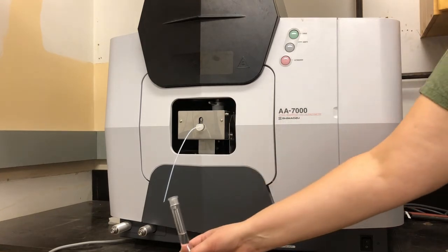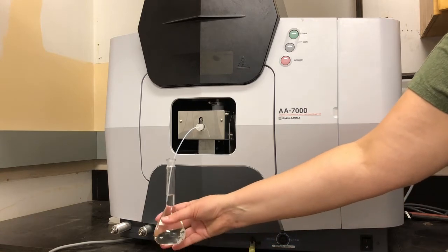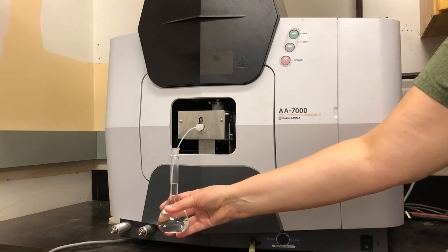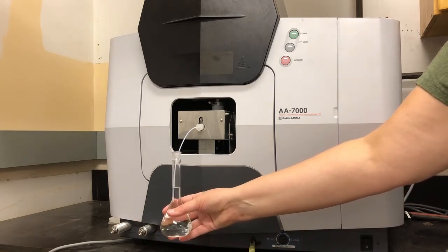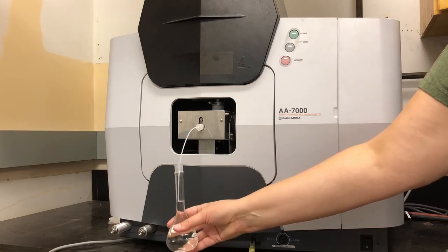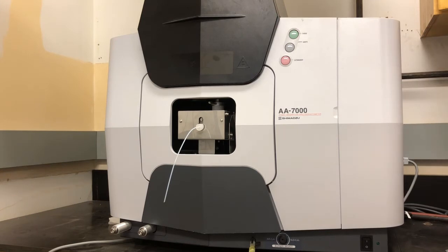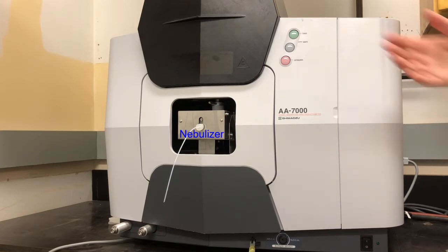So we simply take our flask containing our sample or our standard, and we gently place the tube in the sample under the surface of the water, and by capillary action it is taken up into the instrument. So the sample enters the nebulizer, which vaporizes the liquid. It evaporates off the solvent, and then the atoms enter the flame.